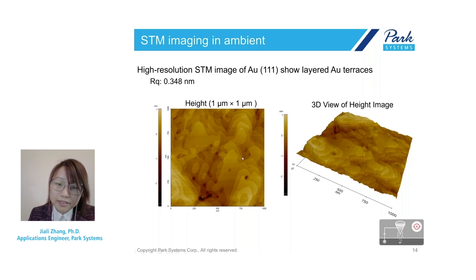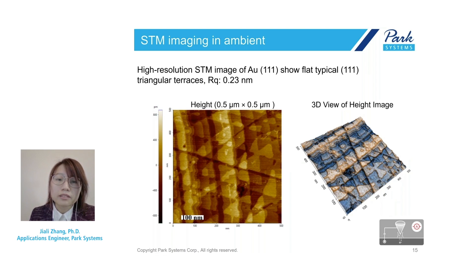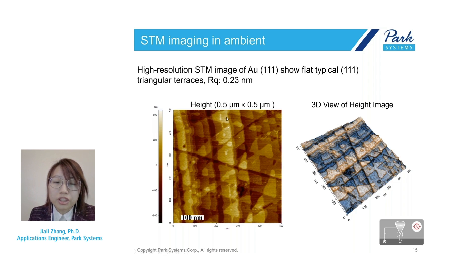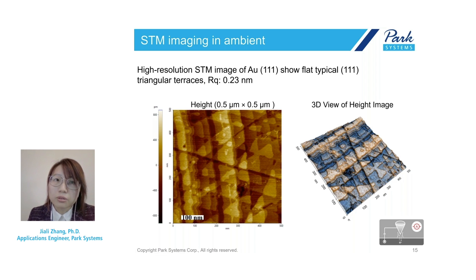Here are high-quality 1×1 µm height images acquired by our STM module on the NX10 system, with 3D views on the right side. You can clearly see the different layers of gold terraces and gold islands, with a roughness of about 3.48 ångströms. Zooming into a 500×500 nm area, we can see the 60-degree angle of the gold (111) terrace edge — a characteristic of epitaxial gold (111) orientation not usually observed in other AFM systems. The 3D display also shows the terraces are separated by well-defined gold steps with a roughness of about 2.3 ångströms.